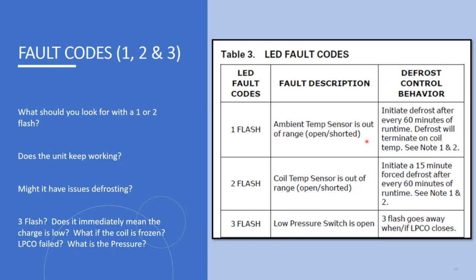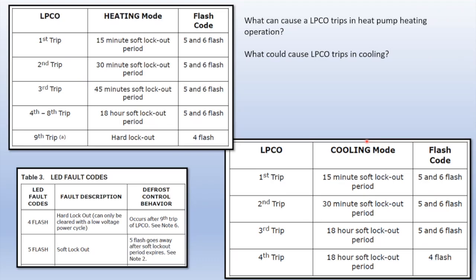So a 2 flash means the coil temp sensor is opened or shorted. Again, it doesn't mean that it's out of calibration, it's a direct open or short. And it's going to initiate a forced defrost for 15 minutes every 60 minutes. A 3 flash means the low pressure switch is open. The LPCO is the only thing that can initiate a hard lockout, which requires a power reset of the indoor unit, because the defrost board gets all of its power from the 24 volts from the indoor unit.